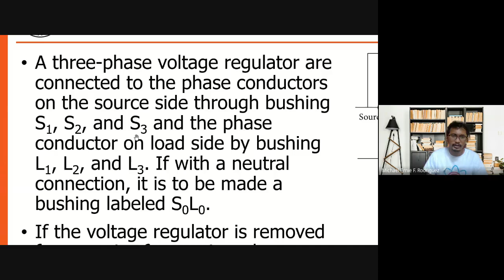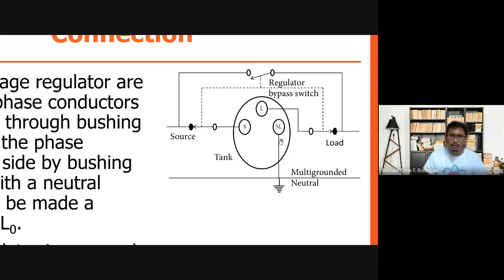A three-phase regulator is connected to the phase conductors, so you have S1, S2, S3 on the source side, and L1, L2, L3 on the load side. If there is a neutral, it is labeled S0 and L0.